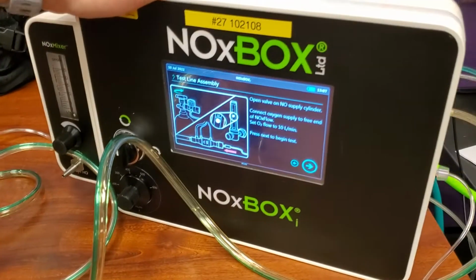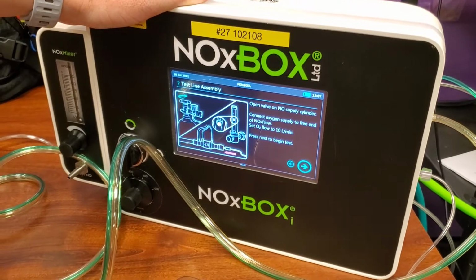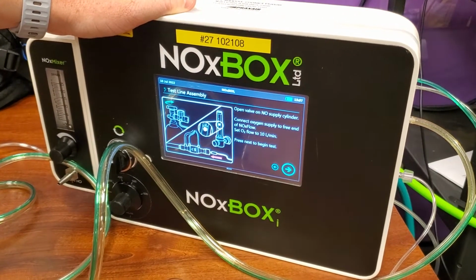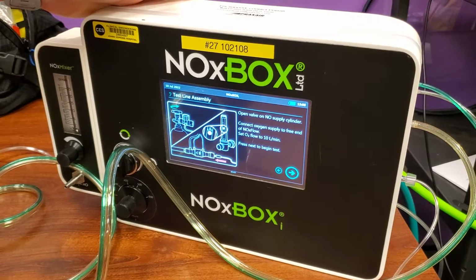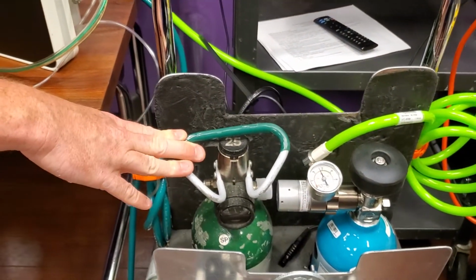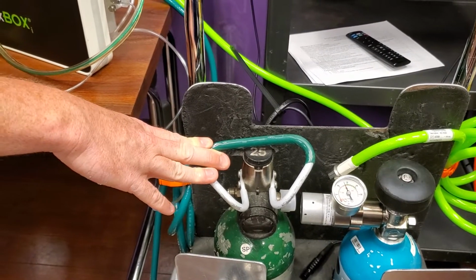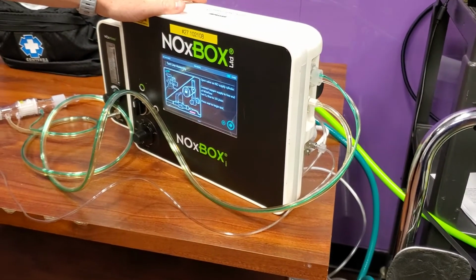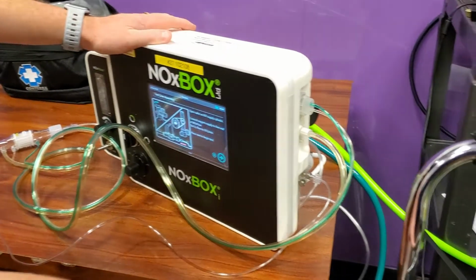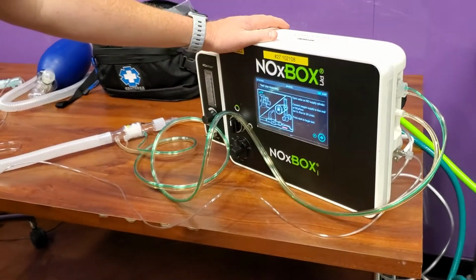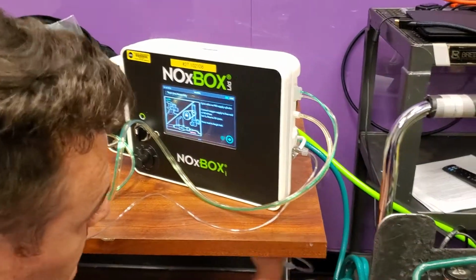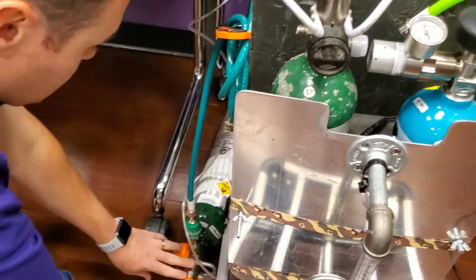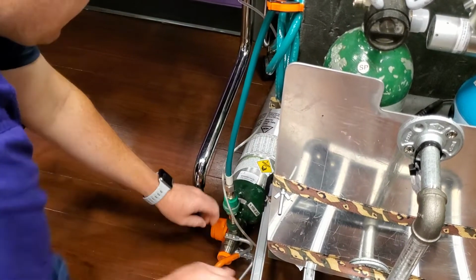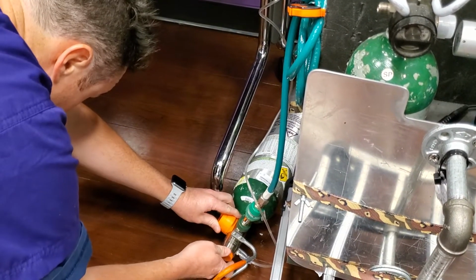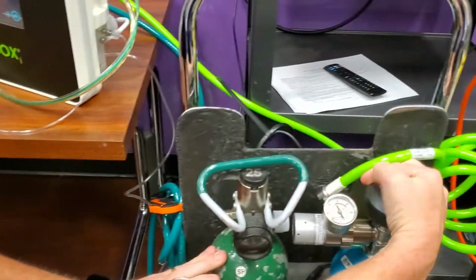And next it's asking us to open the valve on our nitric tank, as well as hooking up to our oxygen bottle here. For when you're at the sending facility, you obviously have your tank here. You do have to set it to 10 liters, so if it takes you a little while to do the system test, you could go through your oxygen a little bit. So if you do have access to one of their cylinders, it might behoove you to make sure that you use that there. In a perfect world, we wouldn't need to use this one, but it's there in case we did need to bag or anything like that. So obviously, we have this piece here. We'll just go on our cylinder here. We're going to set that to 10 liters. And we're going to open our tank here.